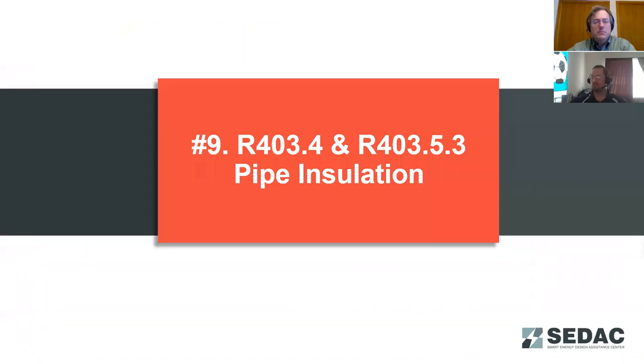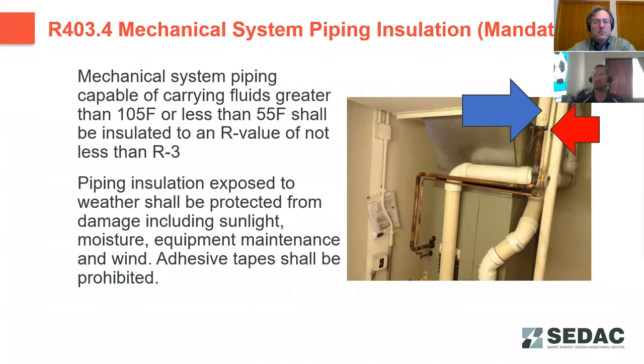Moving on to pipe insulation requirements. Mechanical system piping capable of carrying fluids greater than 105 degrees Fahrenheit or less than 55 shall be insulated to an R value of not less than R3. One of the places that we commonly see missed with this is the hot suction line on AC units, especially where it's running inside the house. Usually it's left uncovered. It should be insulated because that can reach higher temperatures close to or exceeding that 105 degrees Fahrenheit. And also, you're radiating that heat off that pipe back into the house that you're cooling down.